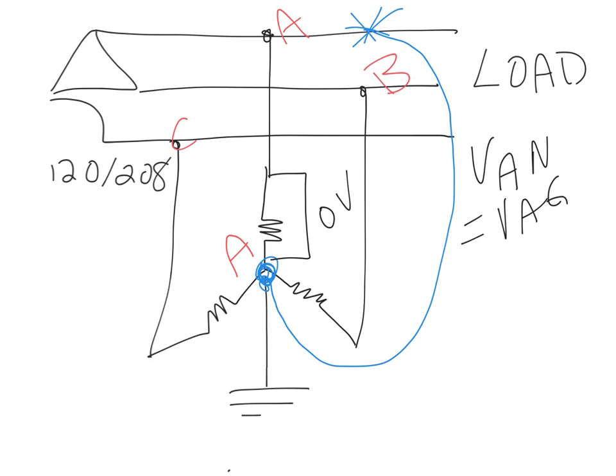So if this point is line A right here and this point is line C right here, we have now placed line voltage across that lamp. So we could say voltage CA is equal to 208 volts. We can also say the same thing over here. When we look at this phase, you can see that B is right here and A is right here. We have now just created voltage B to A, and if you understand, that is 208 volts.